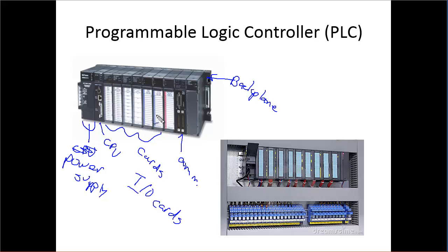So we talked about the analog to digital conversion process and we talked about current loops, right? So there's typically multiple types of IO cards that are available for a PLC. You'll have analog input and output cards and digital input and output cards. So a digital input card, what you would do is you would wire say a push button switch to it, or maybe like a breaker closure or something like that. And so you could sense whether that button was being pushed or whether that breaker was closed. And that would be a digital input, remember our digital inputs are on or off. A digital output would enable you to close a switch. So maybe there's a motor out there or a breaker that you want to close. And so you would close the switch and that would cause the action to happen out in the field.